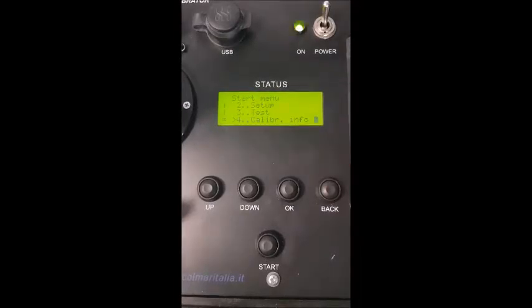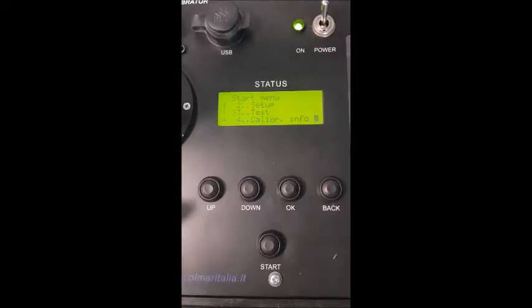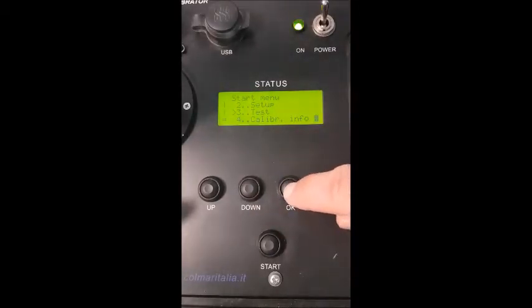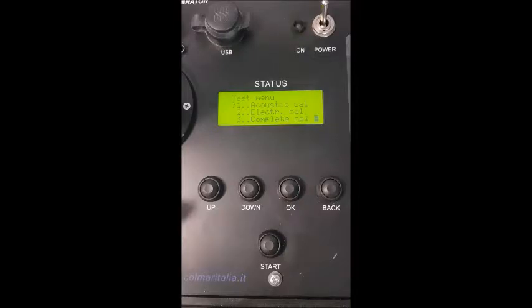The last menu, the fourth menu, is just a calibrator information menu. So it displays some information about the device itself. Let's now have a look at the test menu. This is the most important menu of the device, obviously. Once you access it, you will be able to select one of 3 test modes. The first one is the acoustic calibration mode. Then there is an electric calibration, and then there is a complete calibration. The last one combines both acoustic and electric to do a complete test.